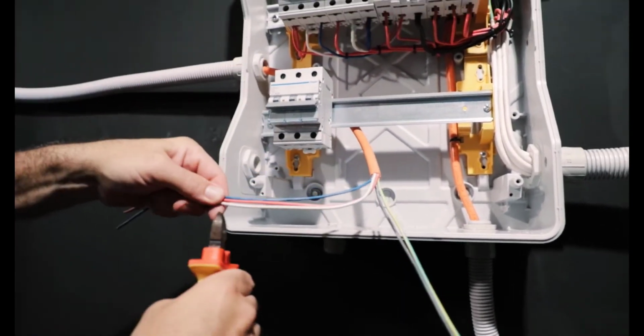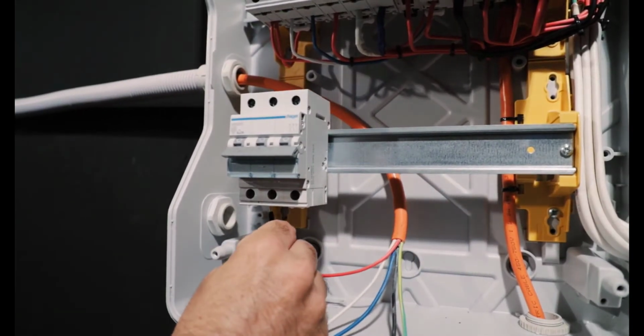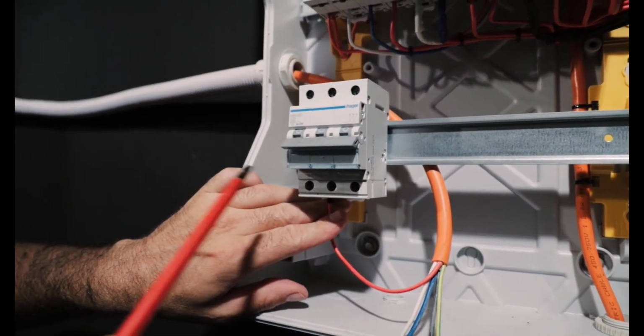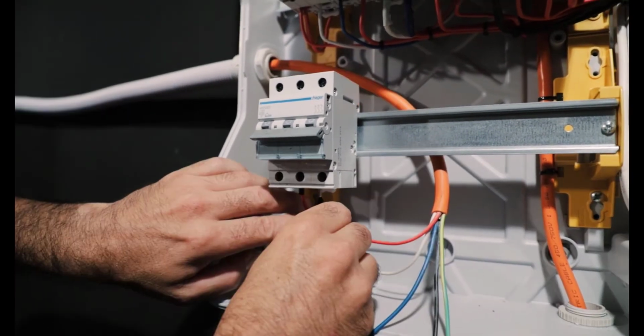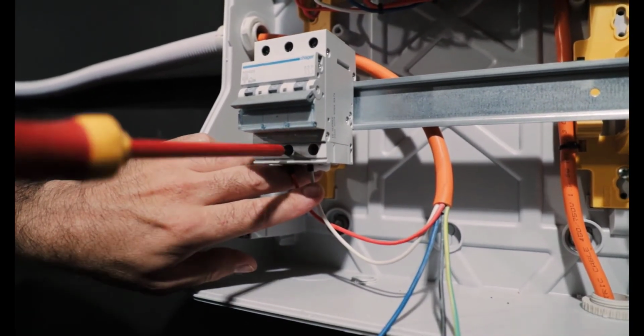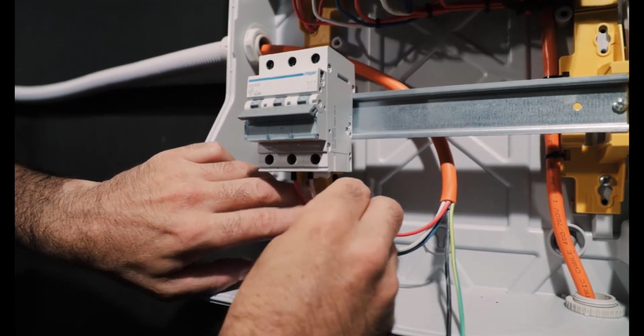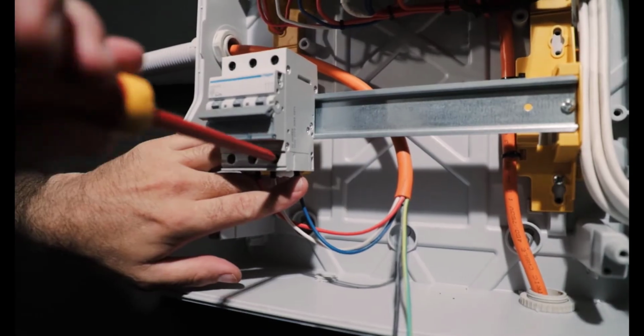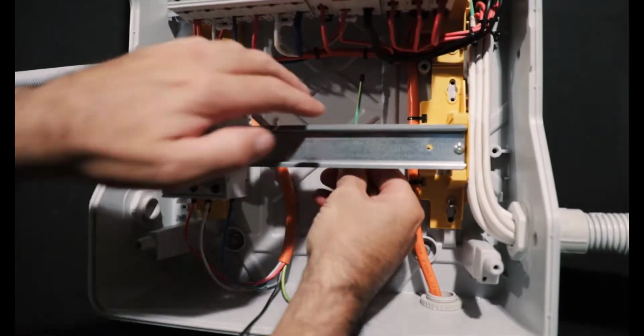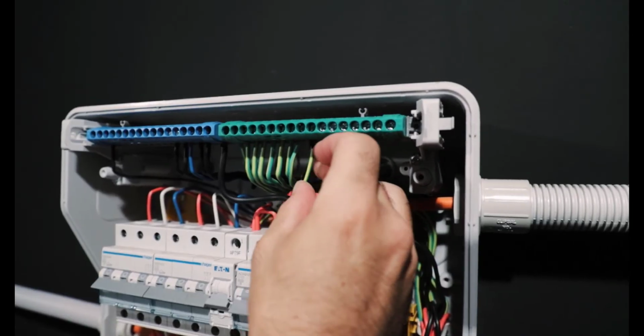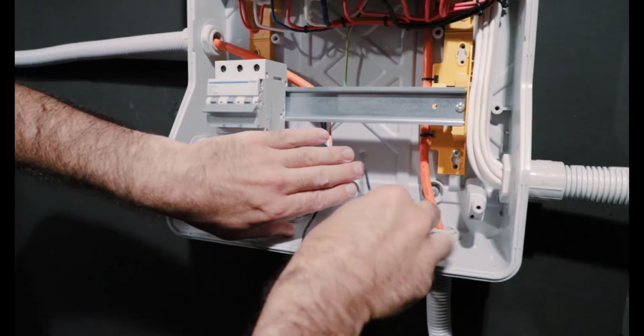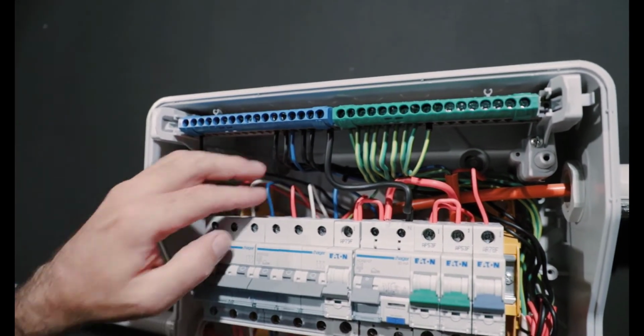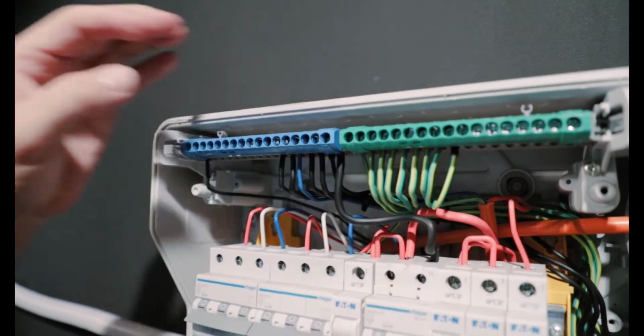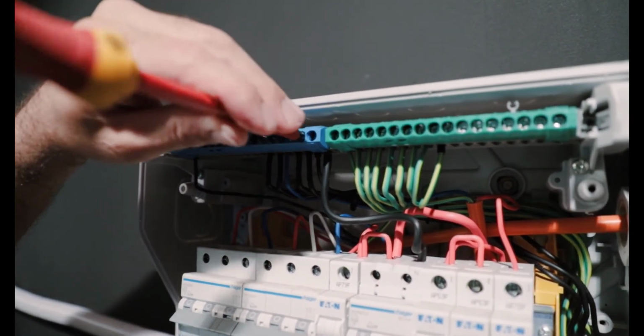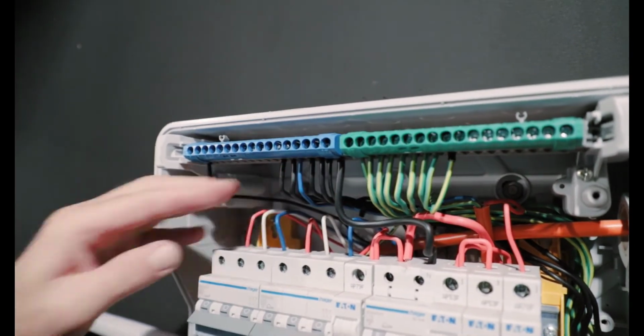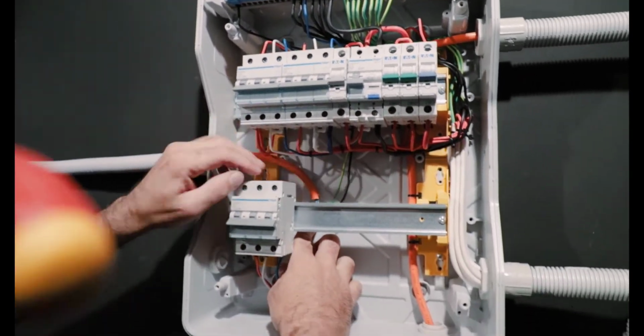Grid measurement is the opposite. We're measuring power flow in and out of the grid, taking into consideration the PV, if it's DC or AC coupled, and then we're calculating the loads, we're calculating the consumption. So it all depends really, at the end of the day, on two things. One, what the customer would like. Is the power flow in and out of the grid the most important thing, or is it the power flow to the actual loads the most important thing? But also, it's to do with how simple it is to wire the installation. So if you've got a nice, new, neat switchboard, like I'm showing you here how to wire, it probably doesn't matter. You might as well do the consumption measurement.